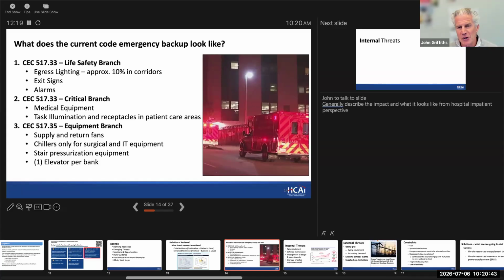You've got 3 branches in the hospital. It's actually fairly basic lighting—in the corridors it's egress lighting, alarms, exit signs, so the building is safe. In medical areas, code minimum means you can operate medical equipment, lighting, some receptacles, and HVAC supply and exhaust. A critical thing to be aware of in a code-minimum hospital is just chillers.